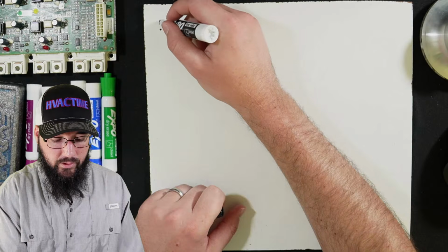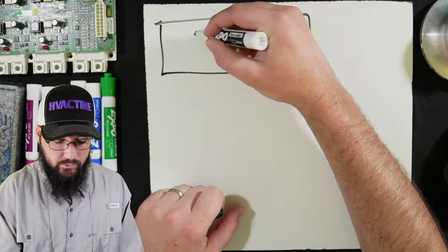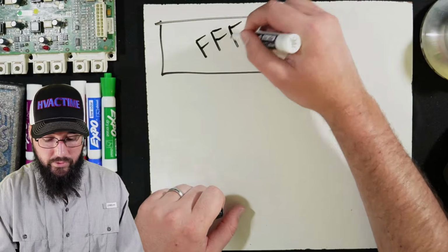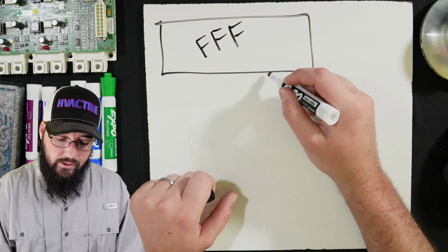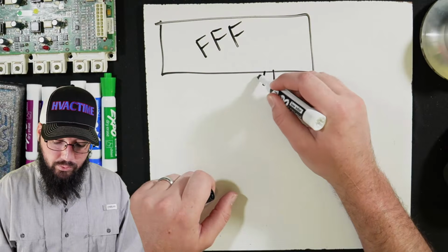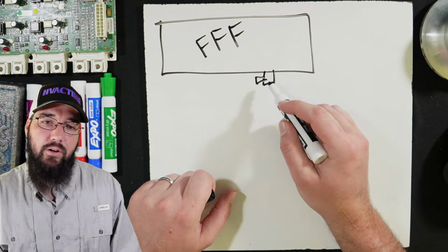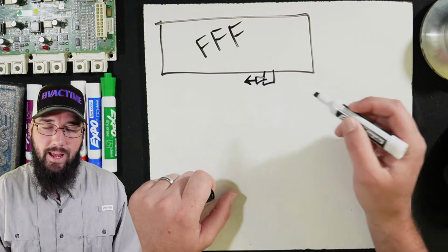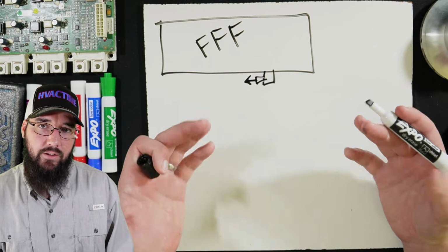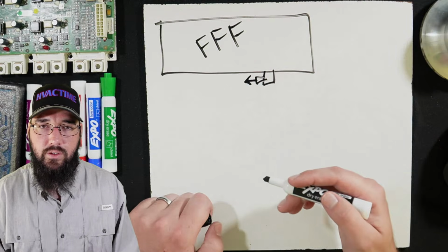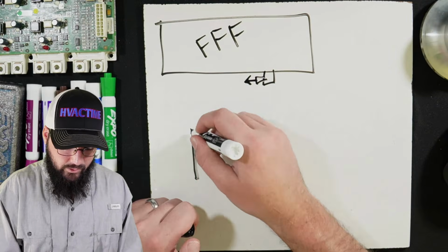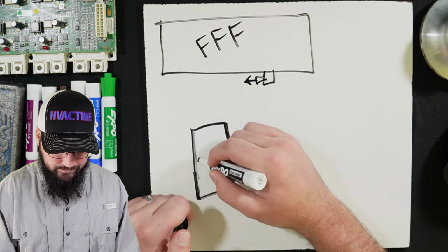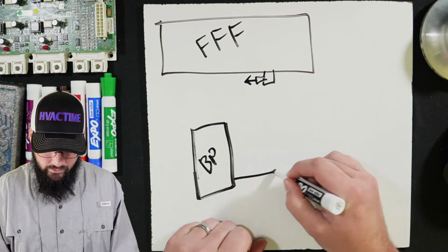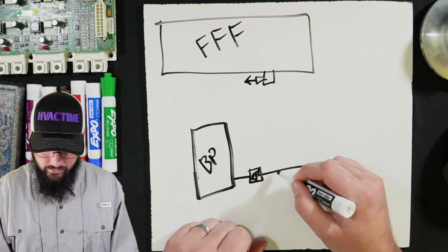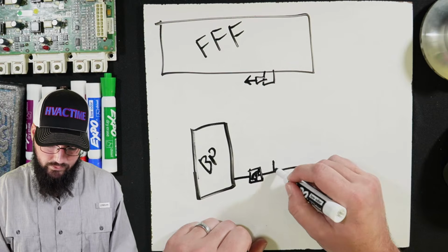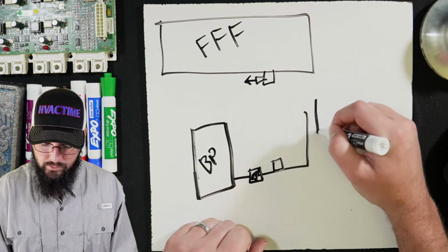So falling film and flooded, okay? So we'll just say FFF, okay, flooded falling film. Pick one. They'll have a service port down here at the bottom of the evaporator. And that's where we can draw that liquid out from. But on these other machines, we can use a CGAM as an example. Those have a brazed plate evaporator. And right here's your metering device, and there is a liquid service right here, and it is kind of down at a lower point, right?